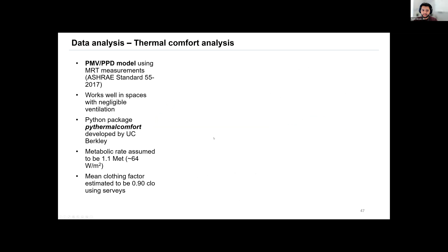We also used that mean radiant temperature to do PMV/PPD analysis per the ASHRAE 55 standard. PMV stands for predicted mean vote, and PPD stands for percentage people dissatisfied. We used the pythermalcomfort package developed by UC Berkeley. Essentially, the closer you are to zero, the more comfortable you are; the more you stray from it, the hotter or colder you feel. For PPD, the lower the percentage, the better; a higher value means more people are thermally discomforted by whatever you're doing.